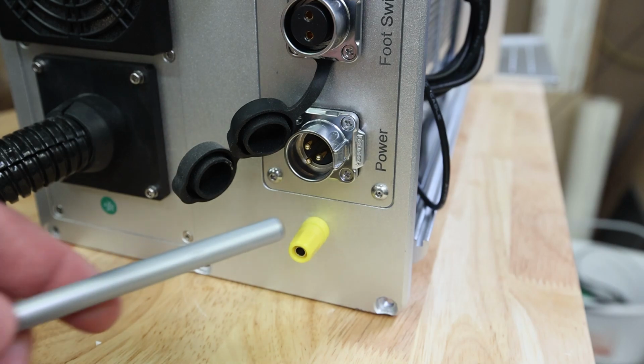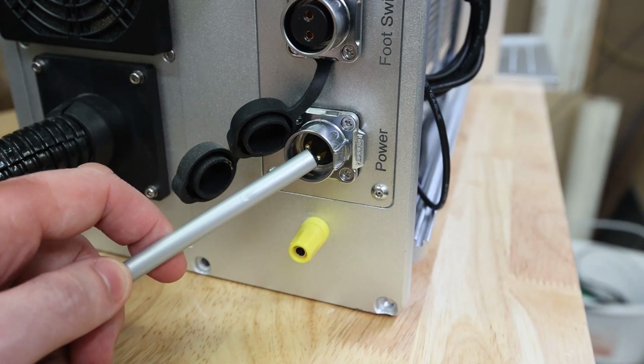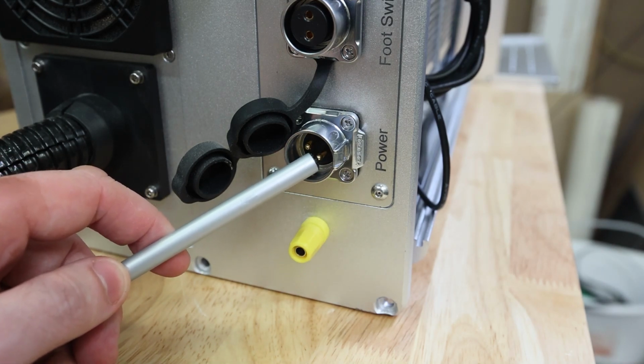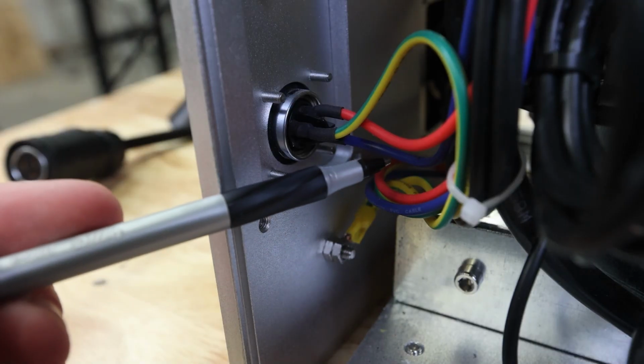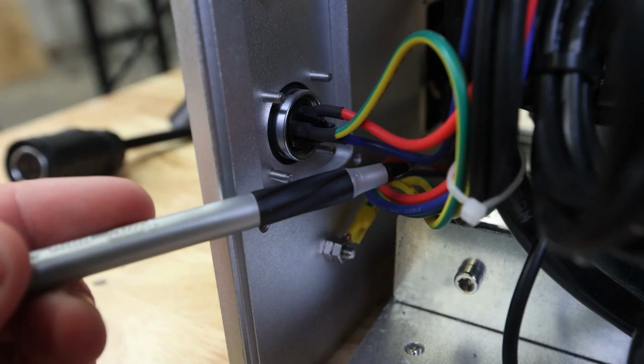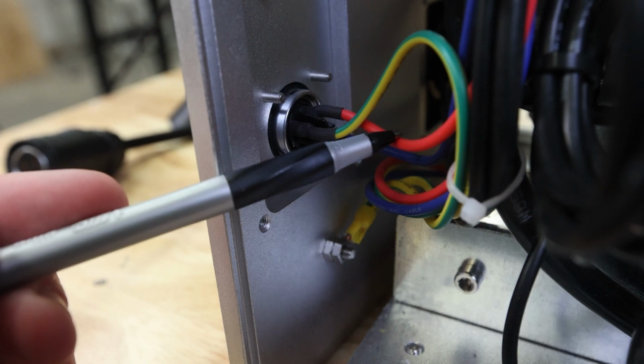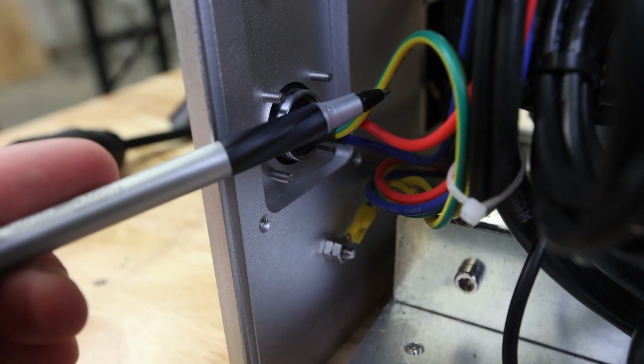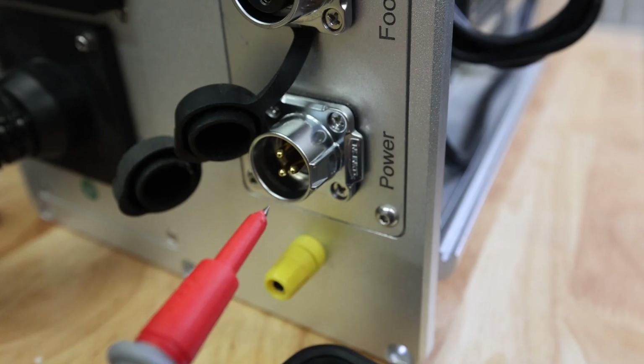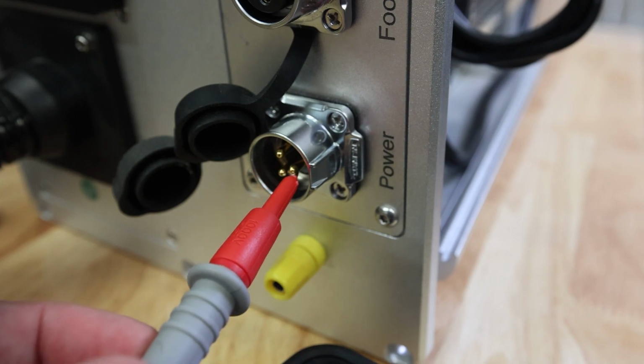To find the exit point, we'll take a look at the inside of the back of the machine, where we plug it into the wall. On the back of this connector, we will find a blue neutral wire, the red line wire, and the yellow ground wire. Looking at the reverse side, it's easy to tell which of the prongs connects to the ground wire. Once the electricity has reached this point, we can assume it has safely left the machine to ground, so this will be our primary testing point.